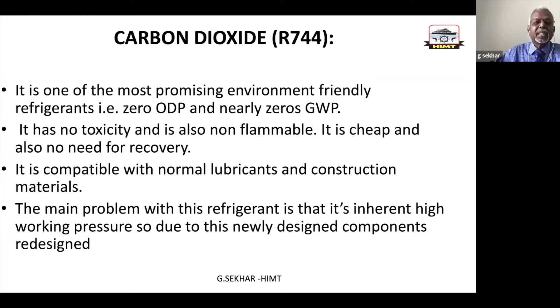So basically now, when you look at the refrigerant properties or the qualities, what are all the qualities? There are some thermodynamic properties required when you select a refrigerant. We are looking at latent heat of vaporization, low boiling point, freezing point, and of course condenser pressures and critical temperature and pressure. As I have told you, carbon dioxide has got 31. That means in case the seawater temperature happens to be 34, then if you use carbon dioxide, it's not going to condense in the condenser. So you'll not be able to use it.